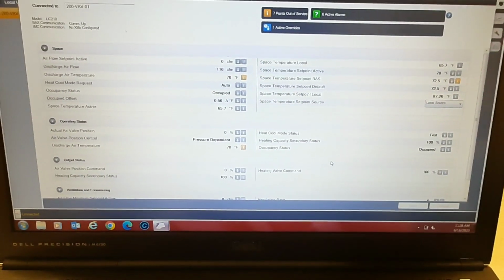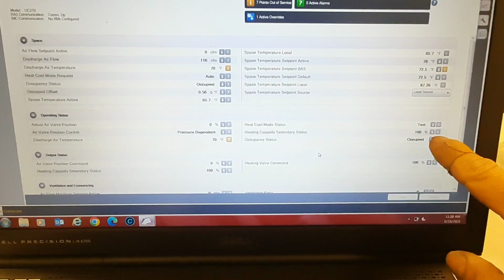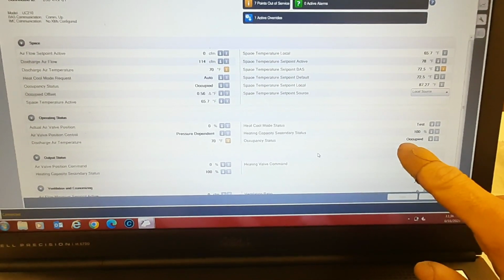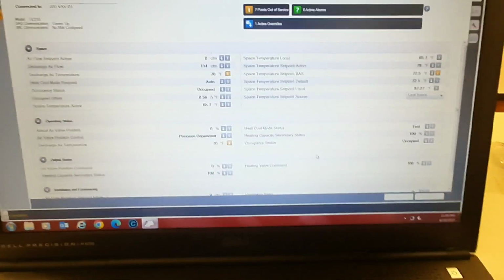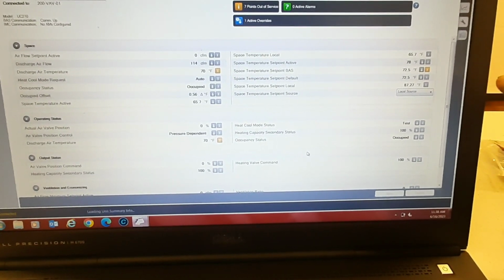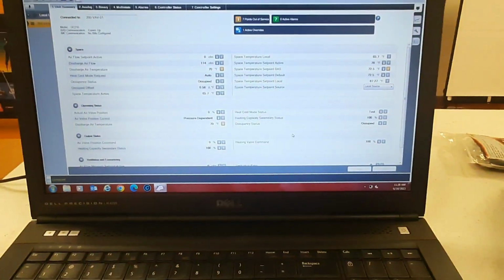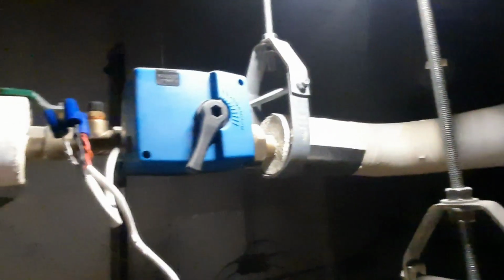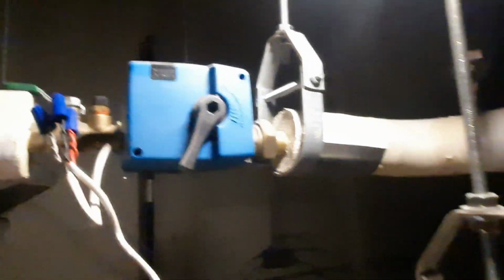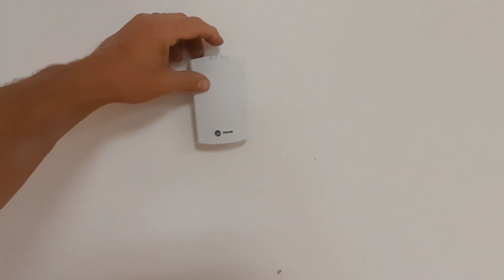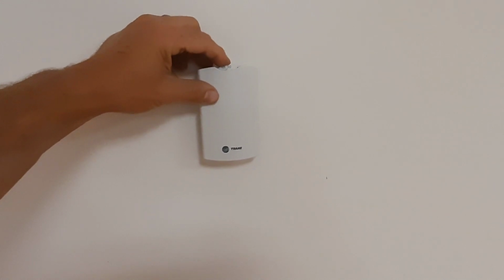So we are in normal operation now. I don't know why I'm still showing tests, but my heating valve, I'm calling for 100% because I got my thermostat cranked up to 78. And my heating valve is open. So that's at 100%. So that's correct. Might have to go plug into the SC and see if I can't calibrate stuff from there, because I don't know why I won't calibrate, but let's turn it down.